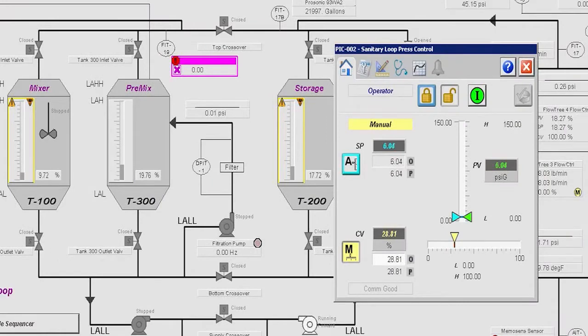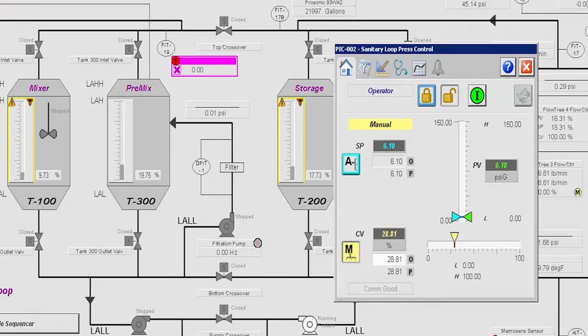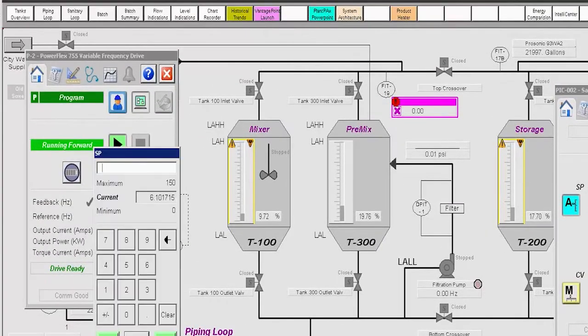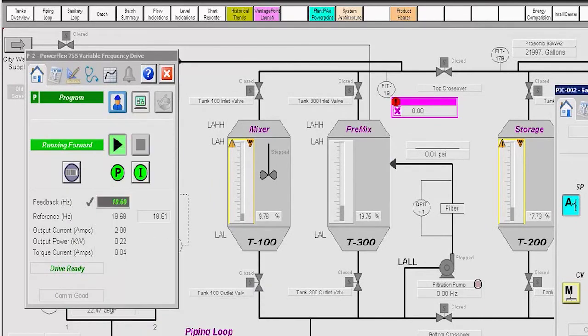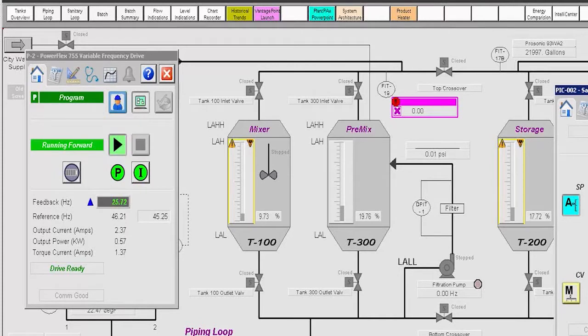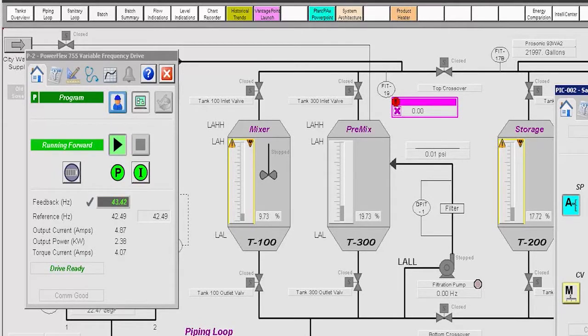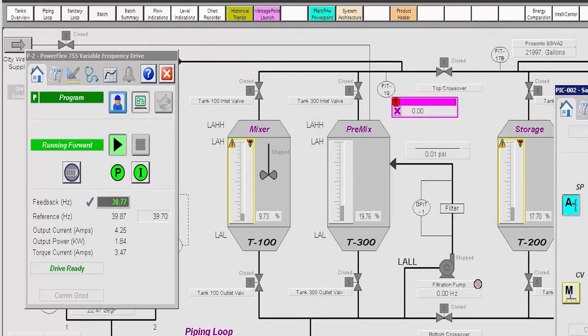We'll place the PID loop into auto mode and adjust the set point to the desired value. When the PID is placed into auto, the PowerFlex 755 transitions from operator mode to program mode and now accepts speed commands from the pressure controller.